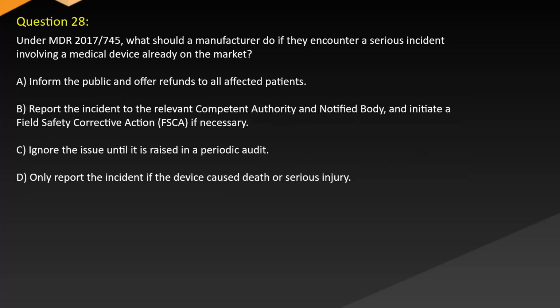Question 28. Under MDR 2017-745, what should a manufacturer do if they encounter a serious incident involving a medical device already on the market? A. Inform the public and offer refunds to all affected patients. B. Report the incident to the relevant competent authority and notified body and initiate a field safety corrective action (FSCA) if necessary. C. Ignore the issue until it is raised in a periodic audit. D. Only report the incident if the device caused death or serious injury.